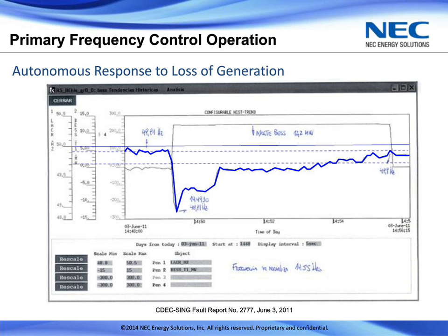Upon that frequency dropping below the minimum point in a predefined deadband around the frequency set point, the GSS then injects all of its power to help stabilize that frequency and bring it back in place. And as you can see, after the GSS comes online, putting its power in discharge mode to support that loss of generation, the frequency starts to recover and then eventually recovers past the set point on the far right of the screen, where the frequency reaches its satisfactory level, and then the GSS shuts off.